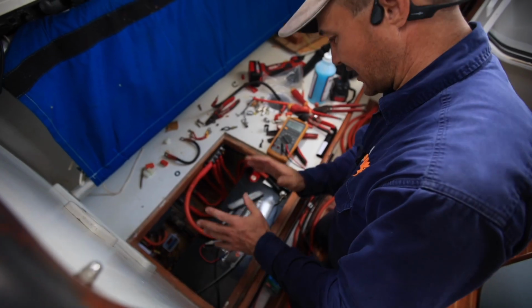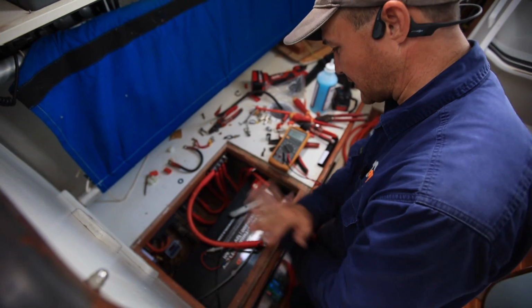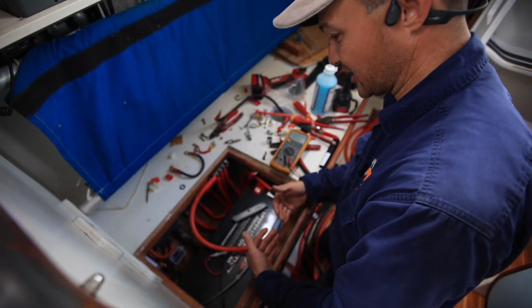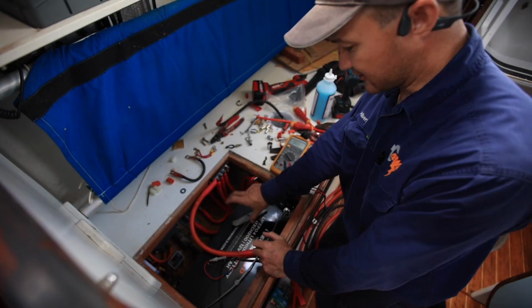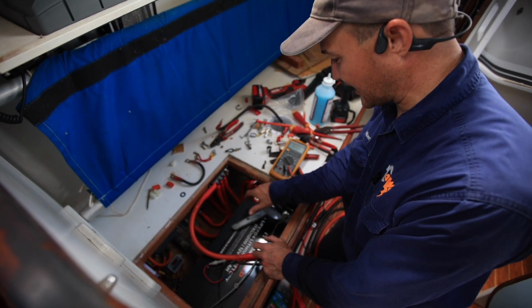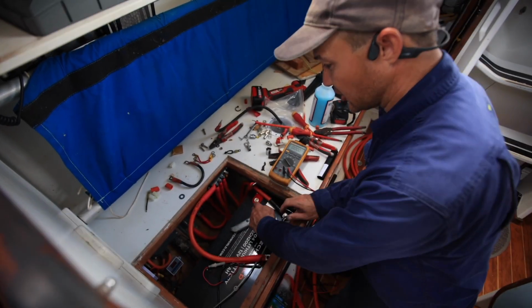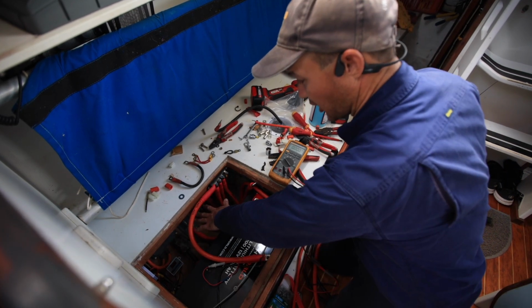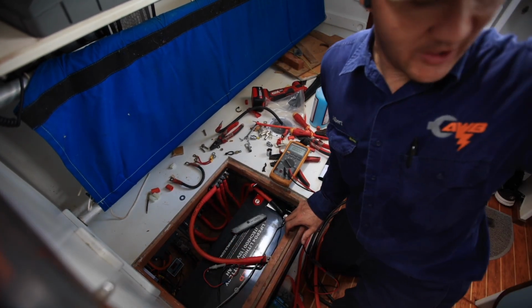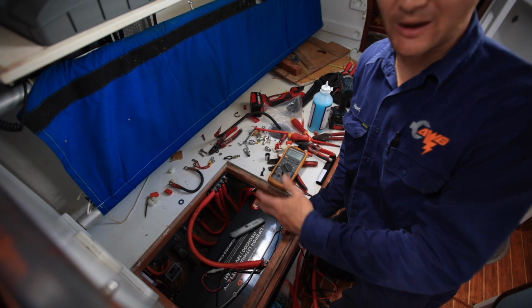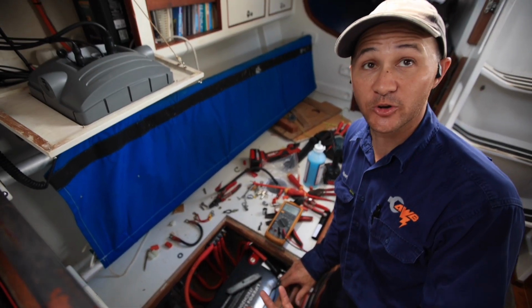That's how it was before, which is very, very bad. That's extremely bad. And it's even worse with lithium, because what happens is this battery will be effectively zero resistance to the bus, to the loads, and then there's the resistance of that lead, which will be like comparing zero to infinity.